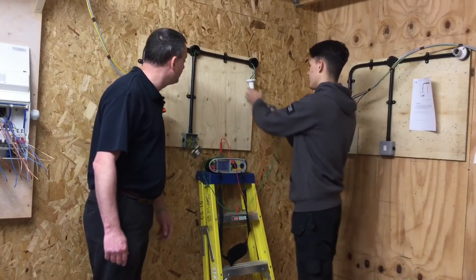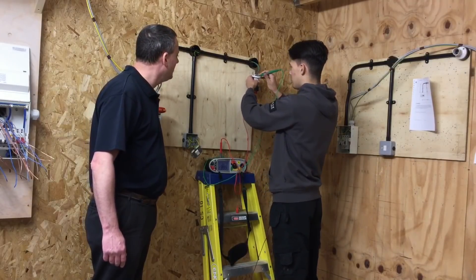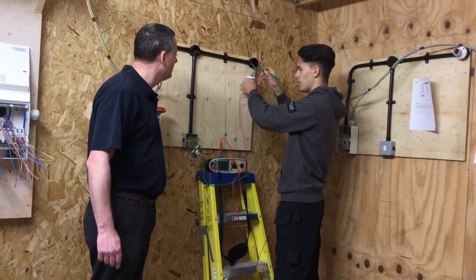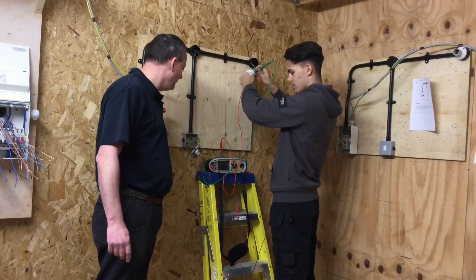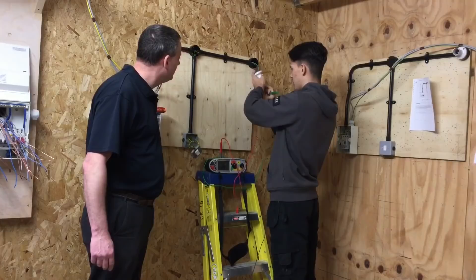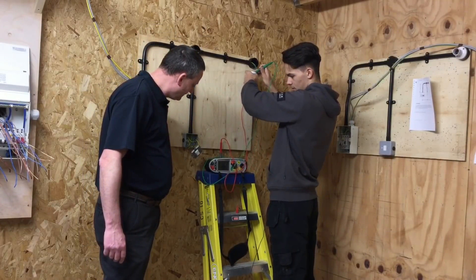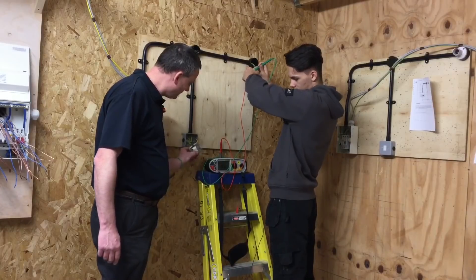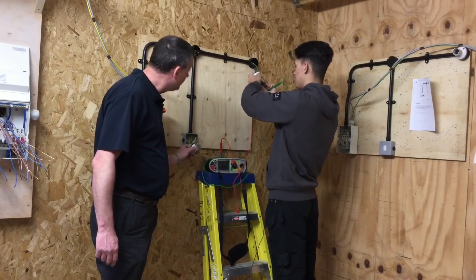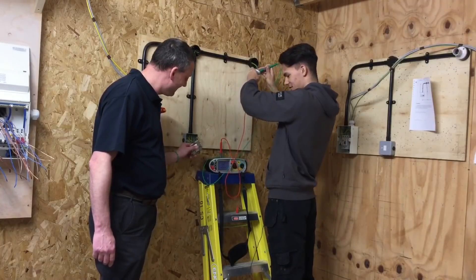We've zeroed out our Kewtech adapter. We're going to the furthest point in the lighting circuit and we're going to record the highest reading in ohms. Let's have a look - we need to switch it around because we're not getting a reading. We're into the pen - switching the light on - still got nothing.